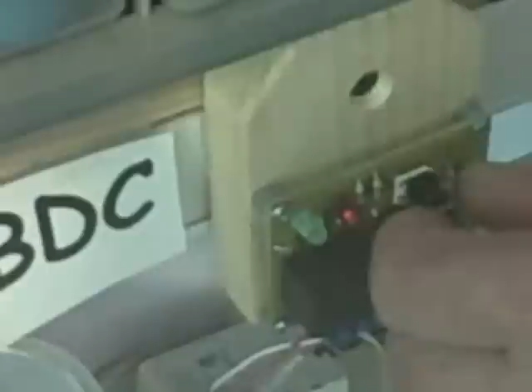So the reason for this adjustment - this is a very simple adjustment for a differential controller. All you have to remember is that if you turn the differential pot counterclockwise, it maximizes the heat collection, but it minimizes the energy conservation. If you want to conserve the energy it takes to run the pump, you turn it more clockwise.